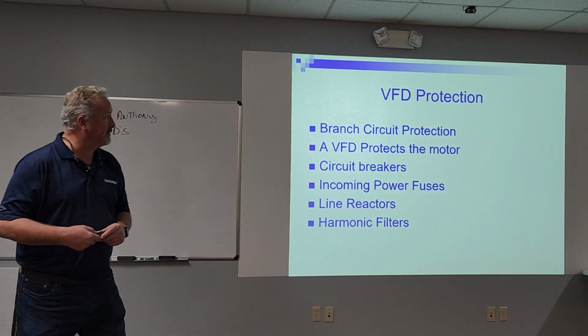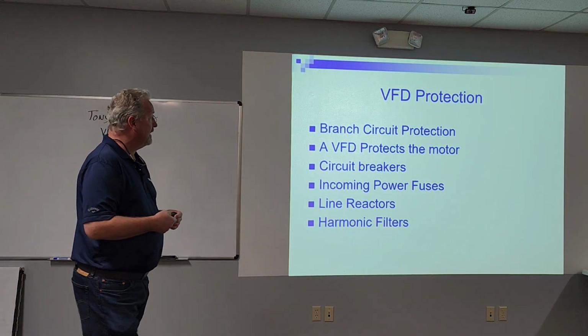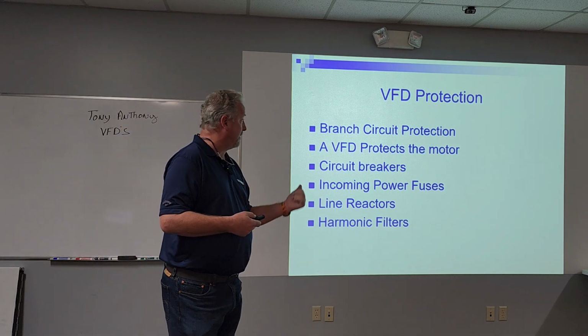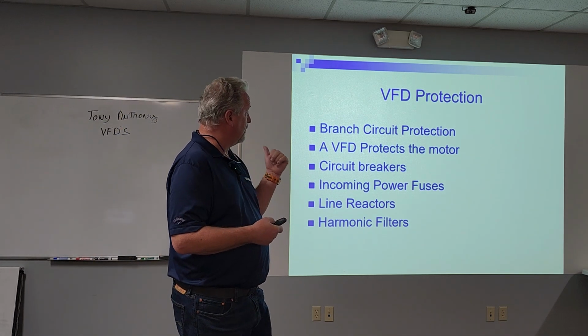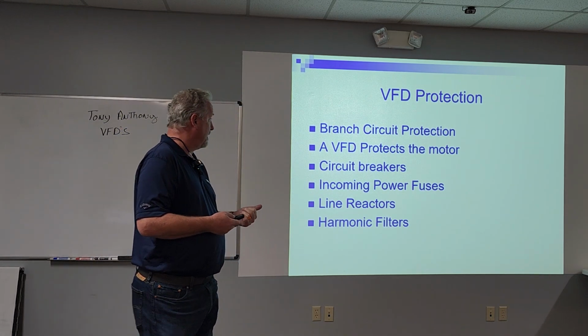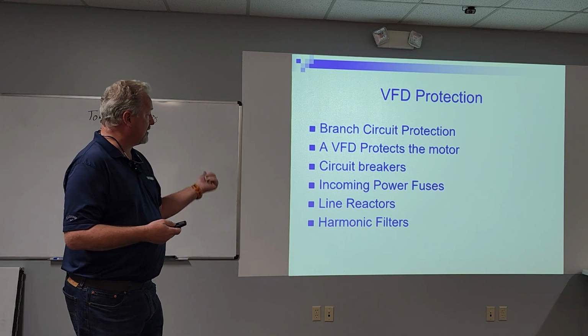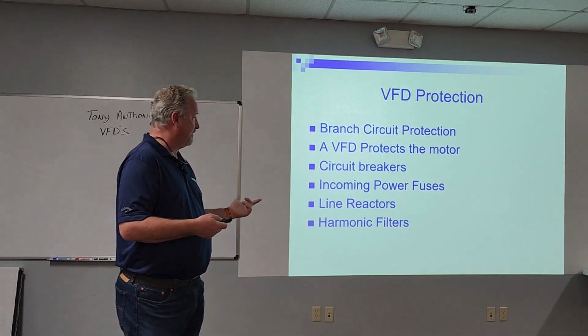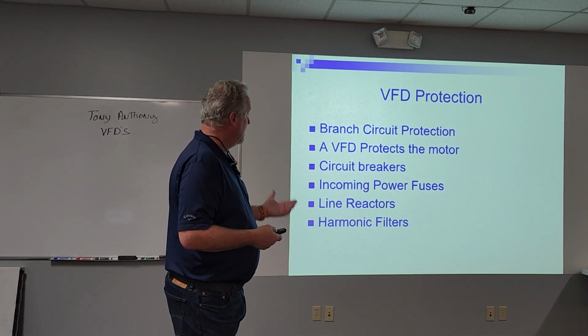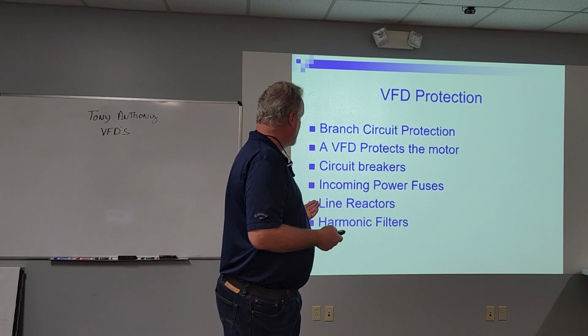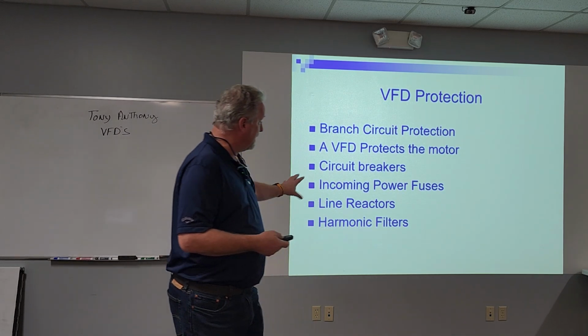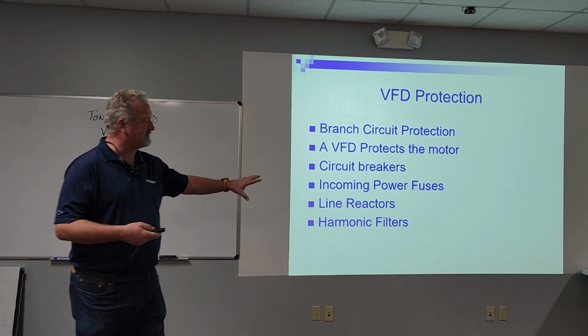What will a VFD do? Protection. We're going to provide some kind of branch circuit protection. We're going to protect that motor. We need circuit breakers, and the circuit breakers will protect the VFD on the input side. We could have fuses and we could have line reactors. And then we got something called harmonic filters, which we'll touch a little bit.